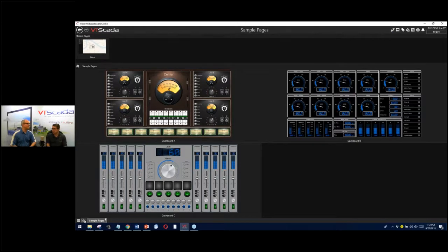That's right. Yeah, it's an extremely important point, that a lot of the time your RTUs and other things are on more limited bandwidth networks. Right. And as you add redundant servers, there are a lot of people out there whose technologies are basically going to poll each RTU for each server. Right. So it's really like having 2 totally separate systems that are actually just doing a watchdog or something between the systems so that they know if one of them went down.